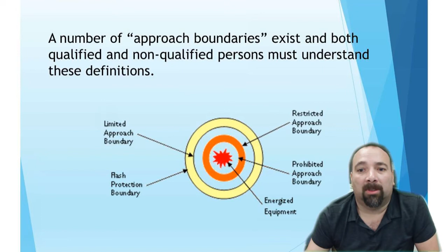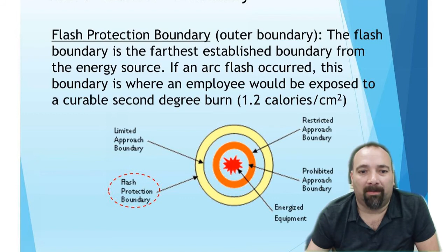The flash protection boundary, or outer boundary, is the farthest established boundary from the energy source. If an arc flash occurred, this boundary is where an employee could be exposed to a curable second-degree burn. Anything closer, it might not be curable.